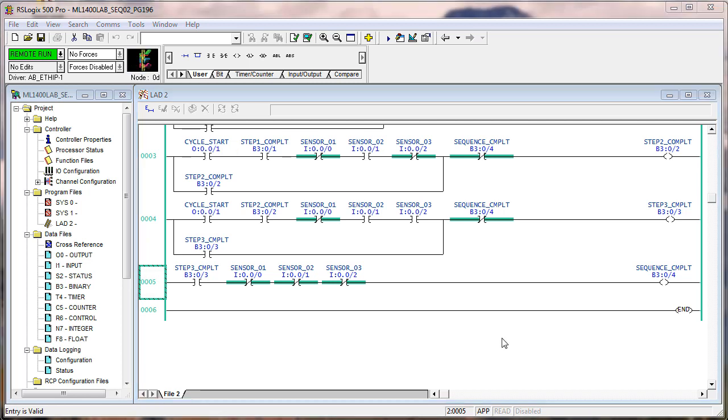The next thing that we discuss is with the latch, unlatch, it had a true execution and no false execution. The rung being false did not execute anything, only a rung true condition. Therefore, when you cycled power or cycled mode, anything that was latched when you left is still latched when you came back. So it maintained the state. Now, in most sequences, you don't want to do that. You want everything to clear when you come back. But we're going to show you how to do that if it's something that you want to do, or to understand why somebody or how they did it.